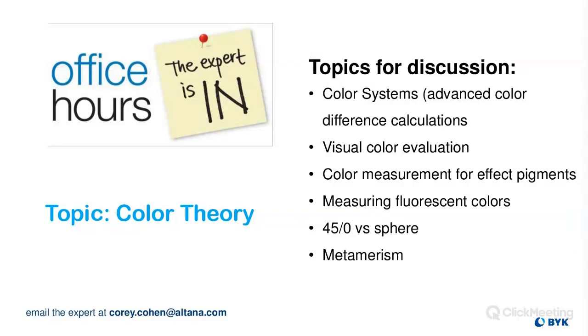So I believe we're talking about a solid colored object, not a transparent object, because there are two types of haze: haze for transparent materials and haze for reflective materials. We do have an instrument that can measure reflection haze, and it is called the haze gloss. It's a benchtop instrument. It measures reflection haze at 20 degrees, which is the standard angle for haze. And it also measures 3-angle gloss.